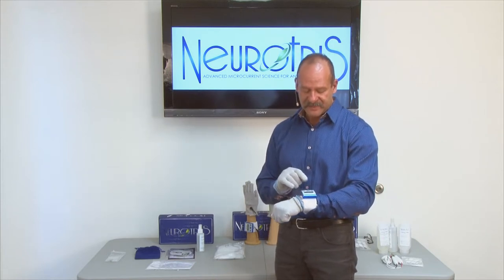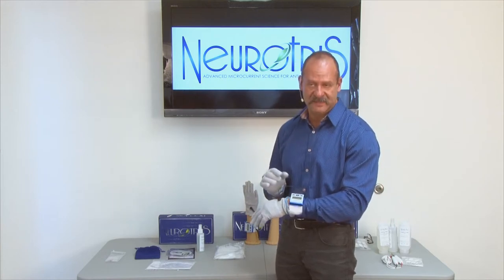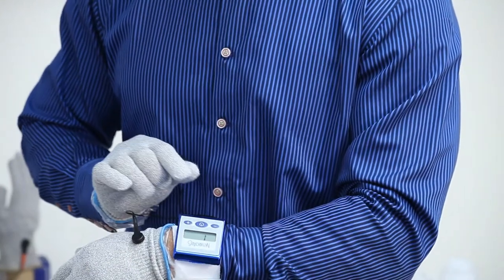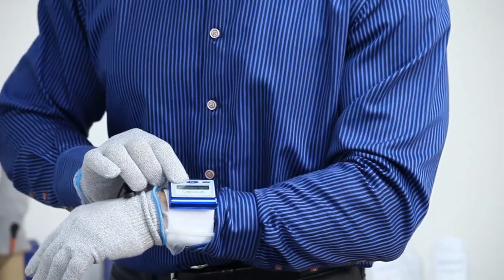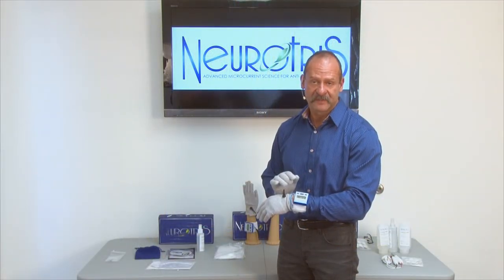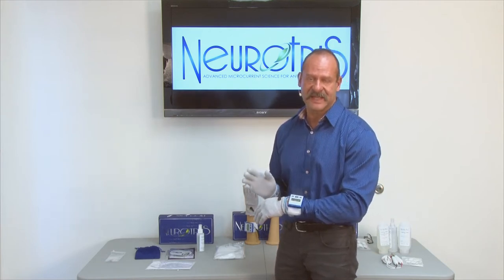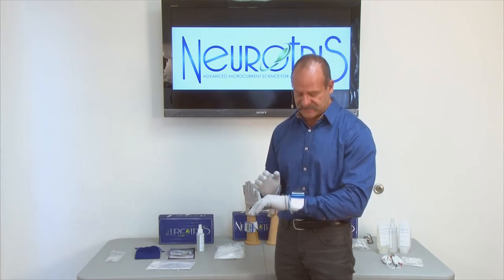To turn the Pico Toner on — hit the center button. This might be upside down for you, but it's how it will be when you see it. Hit the center button — now it's going to flash P1. Start at 15%. In about 20 seconds the screen is going to lock out and you won't be able to make any changes.